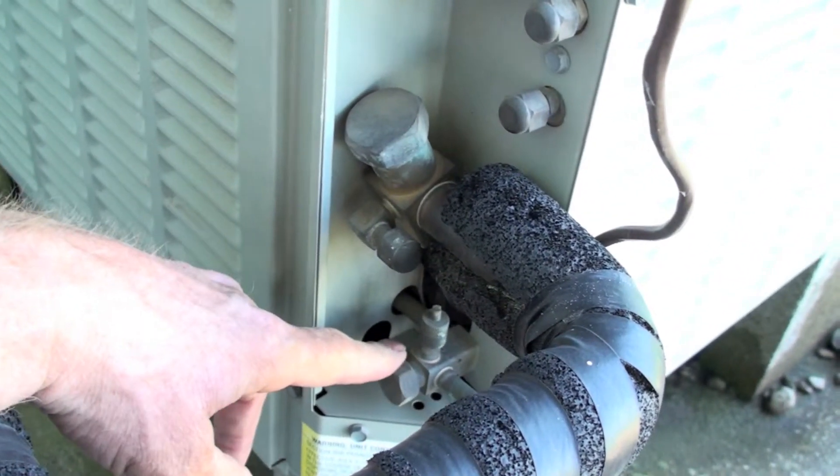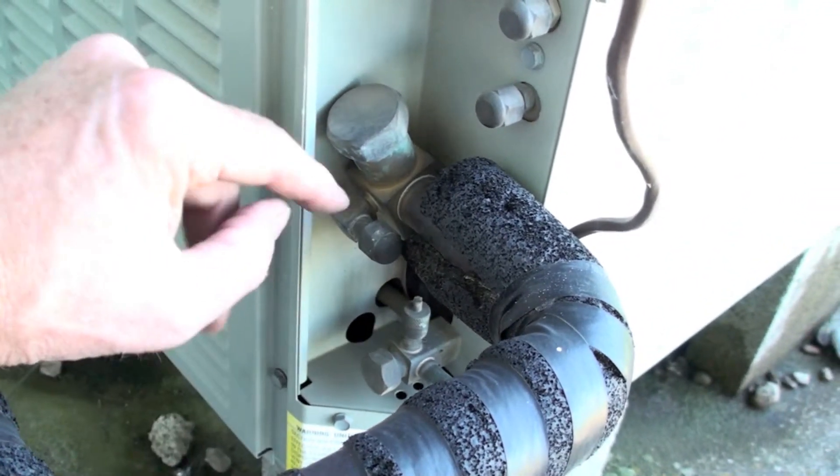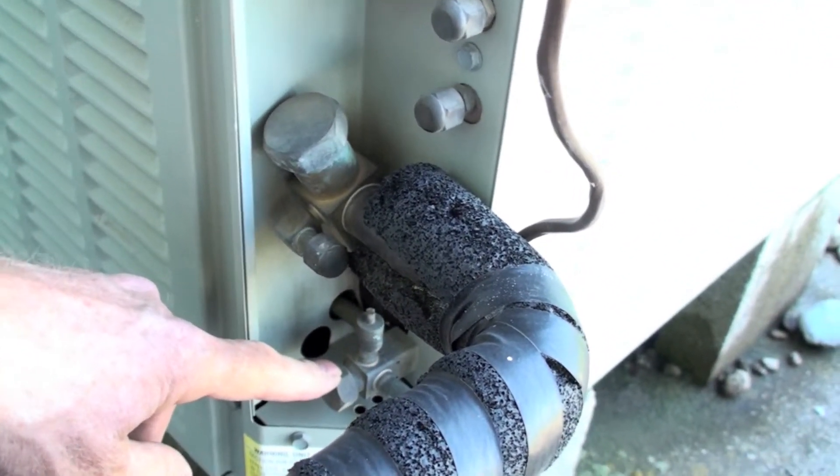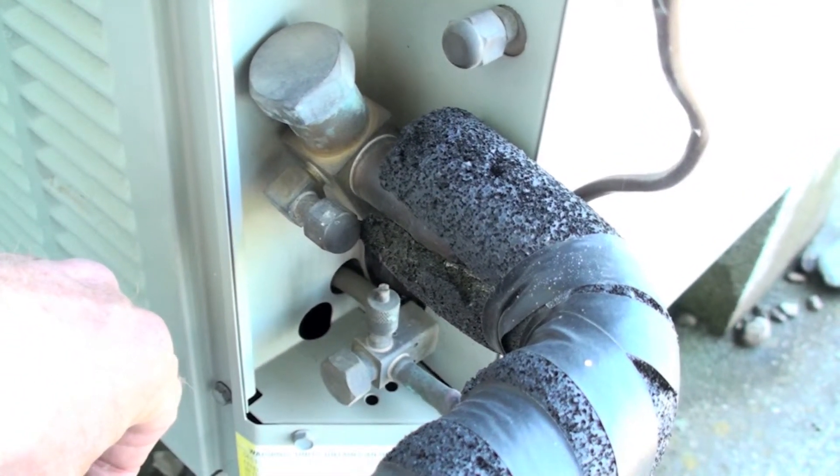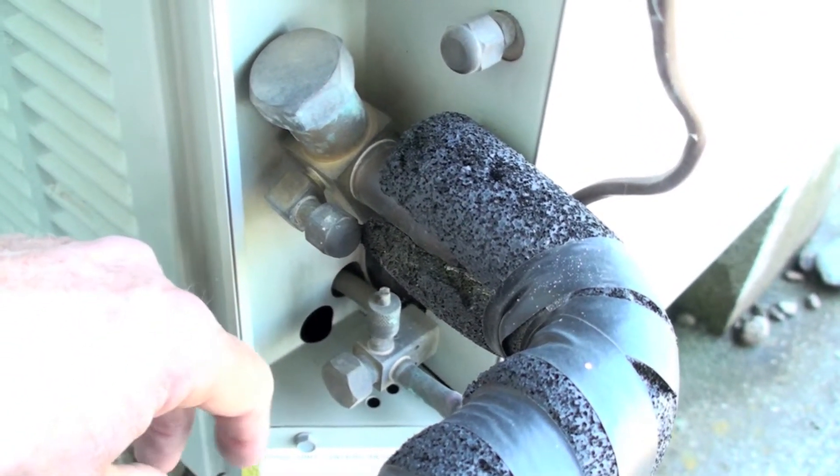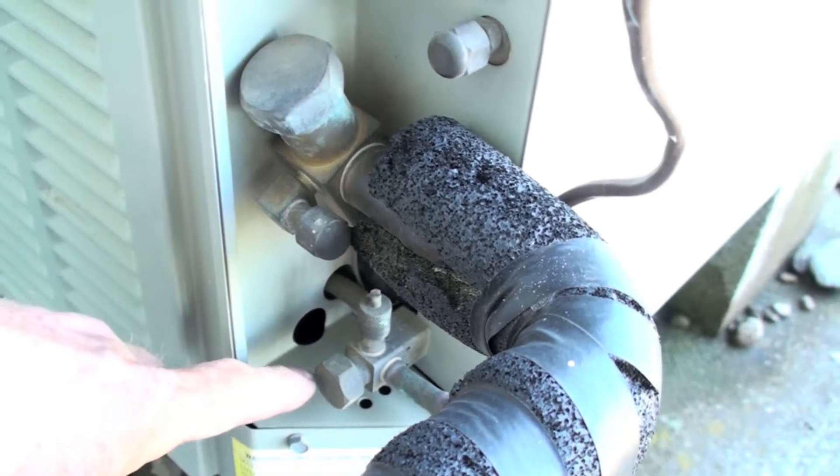And the liquid service valve. We're looking for oil slicks on any of these. Now you can see these are pretty dry. It doesn't seem to be any leakage in these at all. This is what you're looking to see.